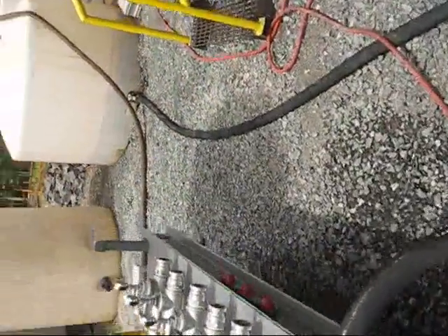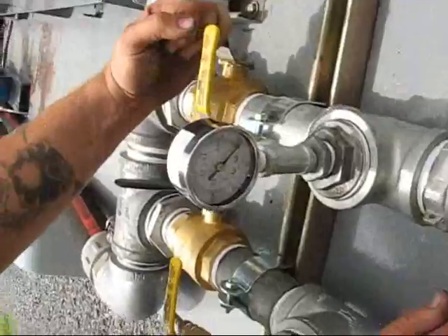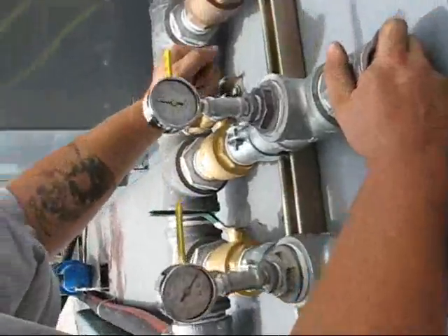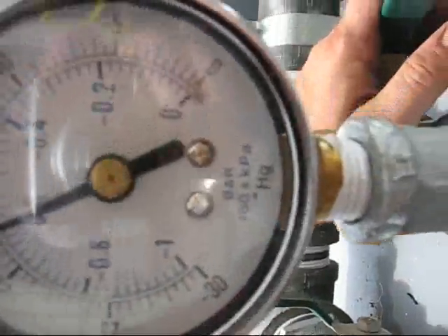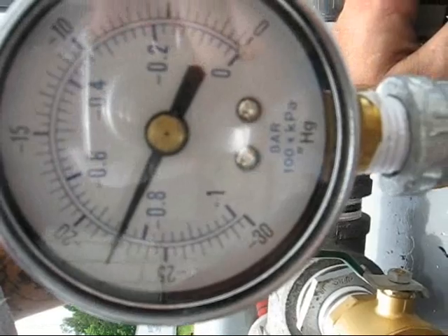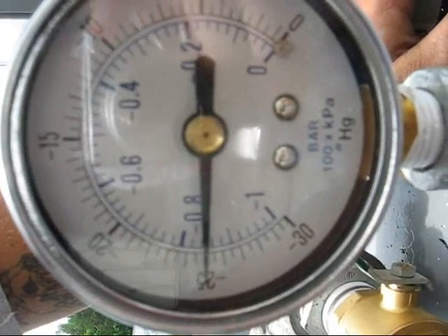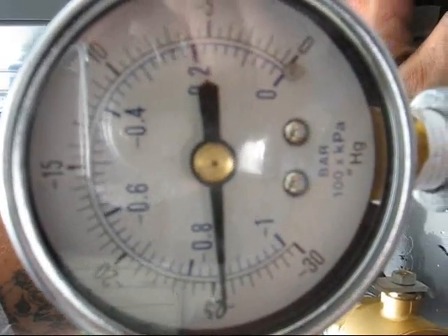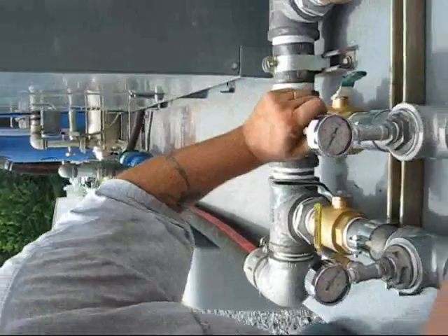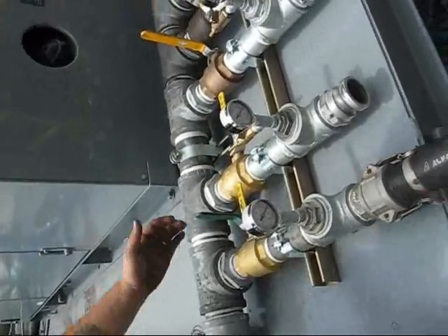The vacuum's up. Turn it off on the water and let's use the air to run the vacuum up. I'm going to show it on the tank. It's about 15 inches... 20... coming up on 25, 26, there's 27, 28 inches of mercury right there. That's good. Okay, that's about it.